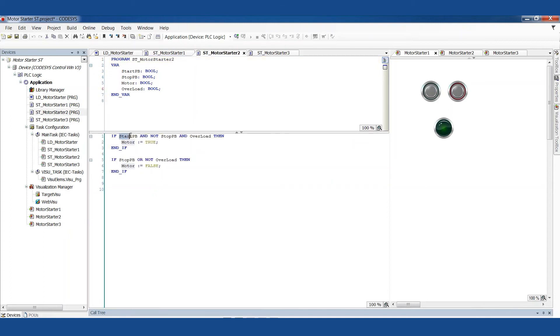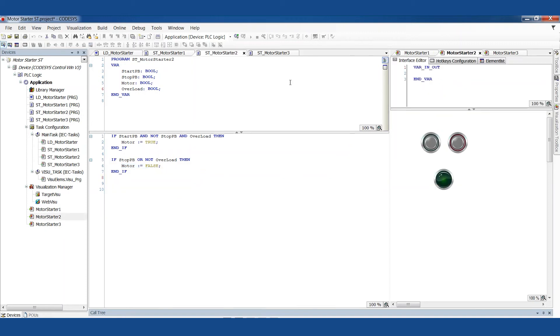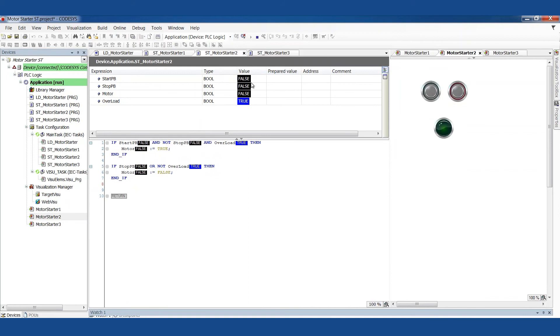So if we push the start button and we're not pushing the stop button and the overload condition is allowing us to run, then turn the motor on. If we push the stop button or the overload condition is not permissive, not permitting us to run, then turn the motor off. Pretty straightforward. Let's run through the simulator so that we can see this run. I've already got the overload in the permissive condition. If I click start, our light turns on, motor is on. And if I click stop, motor turns off.